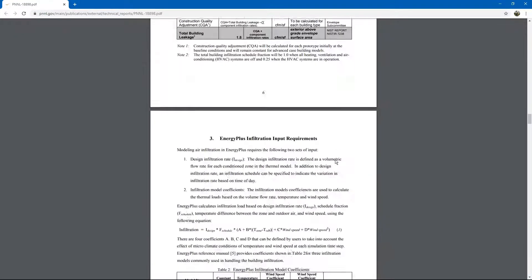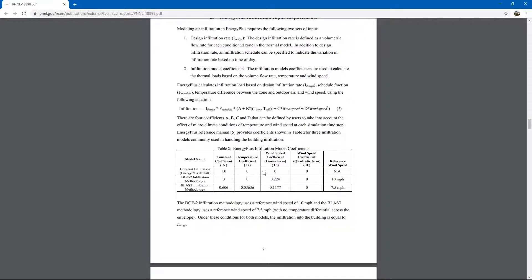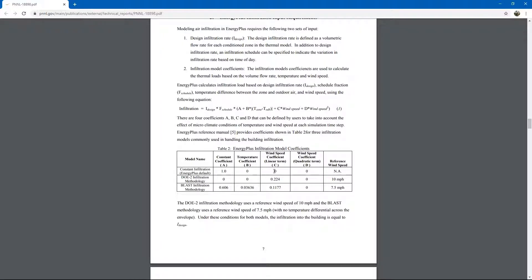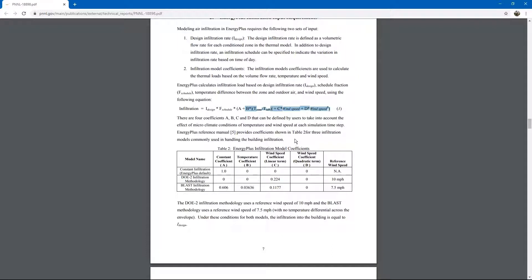These coefficients are used to modify your simulation. Essentially, the default coefficients that are in EnergyPlus and OpenStudio is a coefficient of 1, and all the rest are 0. EnergyPlus and OpenStudio are effectively canceling out all of the temperature difference and wind speed differences. We are strictly designing infiltration based on a schedule. If you do have a building that is sensitive to infiltration based on wind speed and temperature differences, you are probably going to want to change those constants.